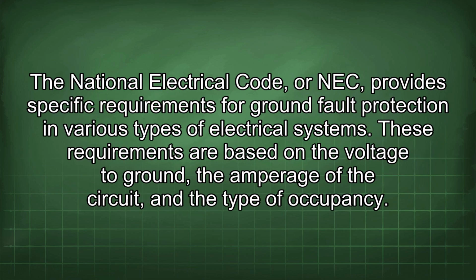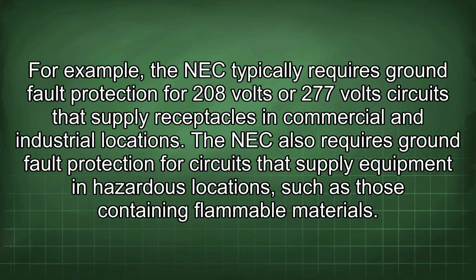The National Electrical Code, or NEC, provides specific requirements for ground fault protection in various types of electrical systems. These requirements are based on the voltage to ground, the amperage of the circuit, and the type of occupancy. For example, the NEC typically requires ground fault protection for 208 volt or 277 volt circuits that supply receptacles in commercial and industrial locations. The NEC also requires ground fault protection for circuits that supply equipment in hazardous locations, such as those containing flammable materials.